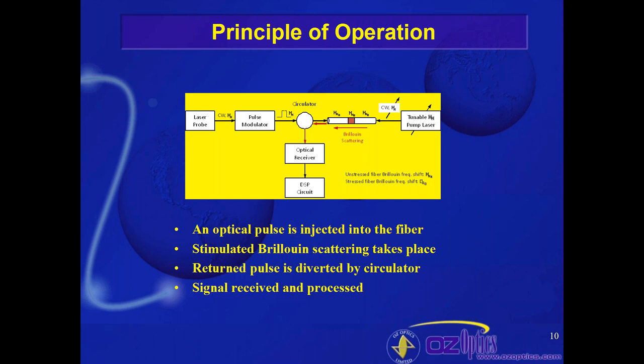This diagram gives a basic layout of how a Brillouin sensor works. We start with a highly stable laser on the left, modulated by a pulse modulator, making very small pulses sent down through the fiber one at a time. As the sharp pulse travels through the fiber, we look for the echo as the light gets reflected back. A circulator allows us to send the light out through the sensing fiber in one direction, and when the light comes back, it sends it to an optical receiver where we analyze frequency intensity versus time.